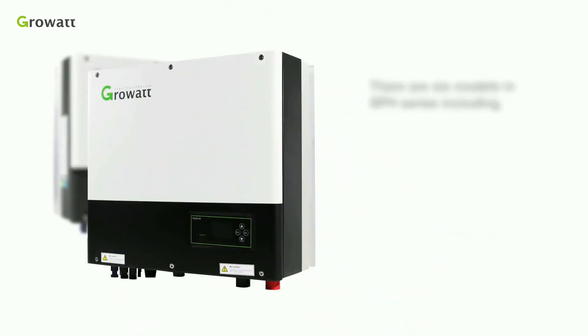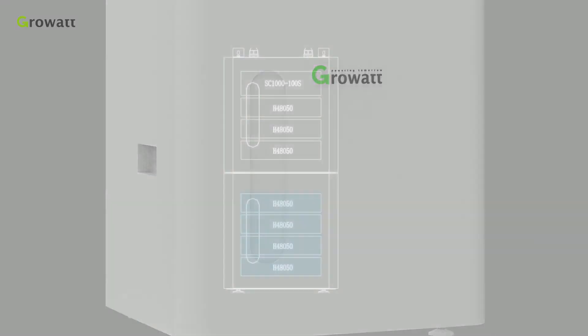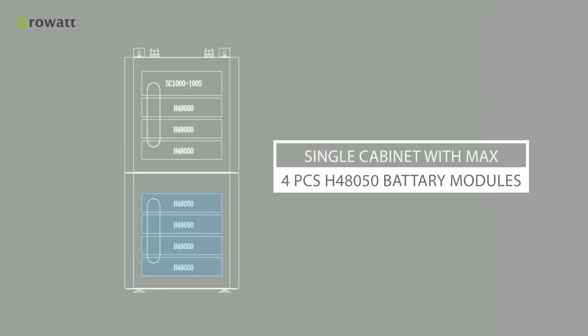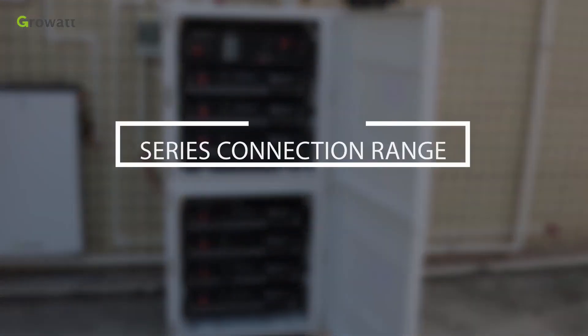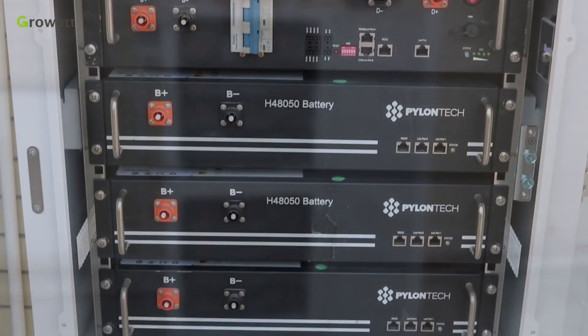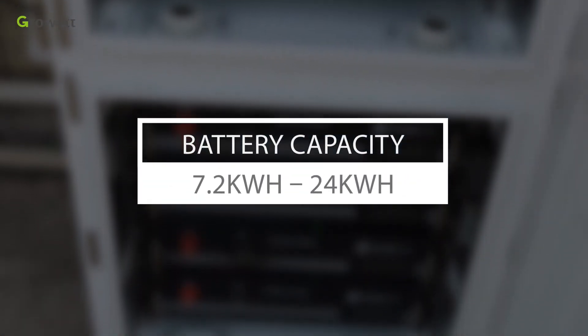There are six models in the SPH series. A single high-voltage battery cabinet can be installed with a maximum of four H48050 battery modules. Each battery module is 2.4 kWh, and the range of battery series connection is from three to ten pieces. The battery cabinets can be stacked up, reaching a capacity range from 7.2 kWh to 24 kWh.